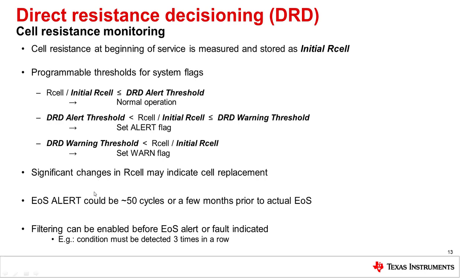These thresholds can be set to give some amount of advanced notice when the cell is approaching the point where it really should be replaced. There is also filtering set up in the device so that you can enable the alert or warning to only be indicated after getting multiple readings above the threshold — for example, two, three, or four readings above the threshold before it actually triggers the alert or warning — preventing false triggers from a single noisy reading.